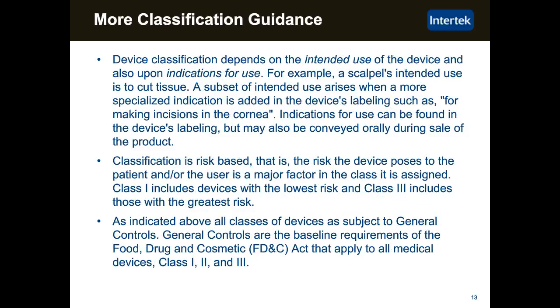A little bit more guidance on classification. Your classification is going to depend on the intended use of the device and also based on the indications for use. An example would be a scalpel's intended use is to cut tissue. A subset of intended uses arise when a more specialized indication is added in the device's labeling, such as for making incisions in the cornea. Indications for use can be found in the device's labeling, but may also be conveyed orally during sale of the product. So in the case of a scalpel that's a general purpose scalpel, that may be a Class 1 device. However, a scalpel that's specifically for making incisions in the cornea may be a Class 2 device based on the higher risk of its indications.